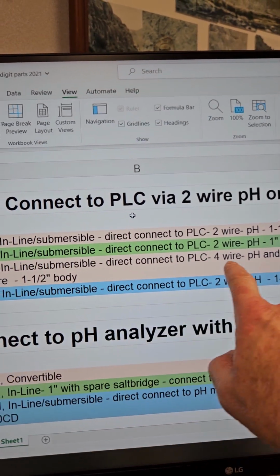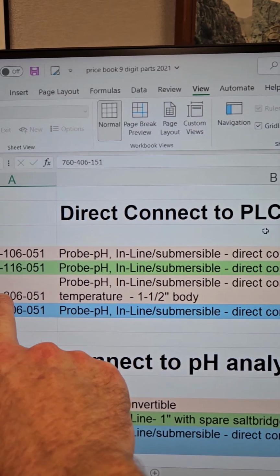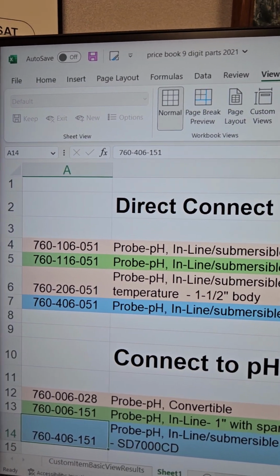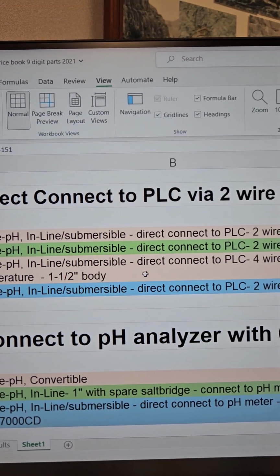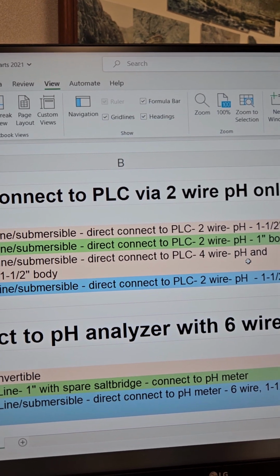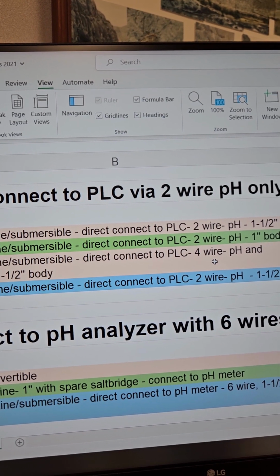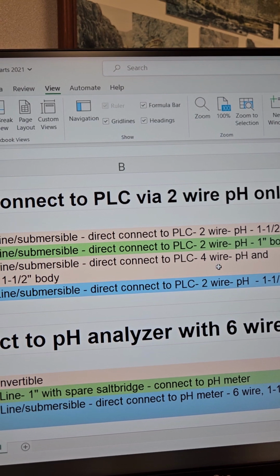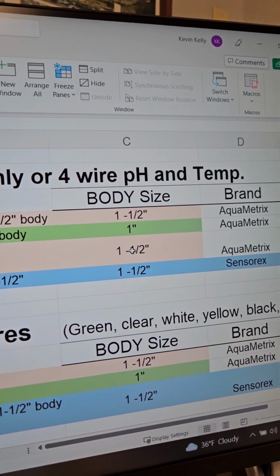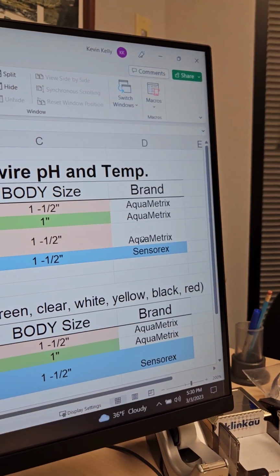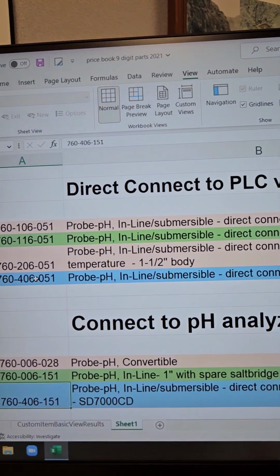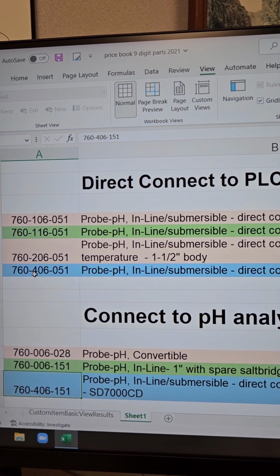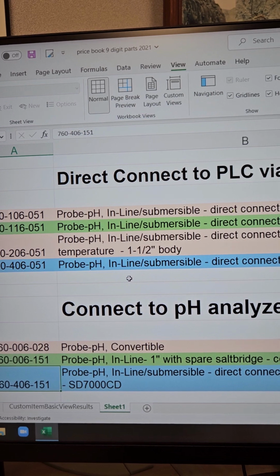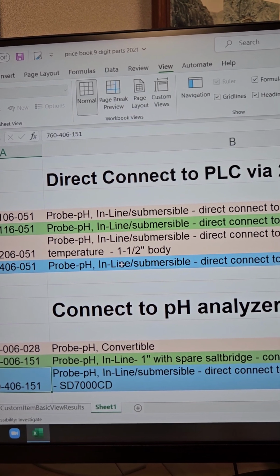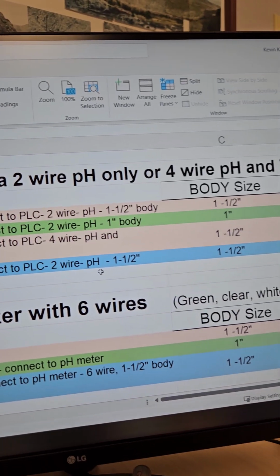And then there is the same probe from AquaMetrix, 760-206-051, that has 4 wires. One pair of wires is for the pH signal, and one's for the temperature signal. Very common. It's a 1.5-inch body, and it's an AquaMetrix probe. Then we have a Sensorex 760-406-051. That probe is also 1.5-inch body, direct connect with 2 wires to a PLC.